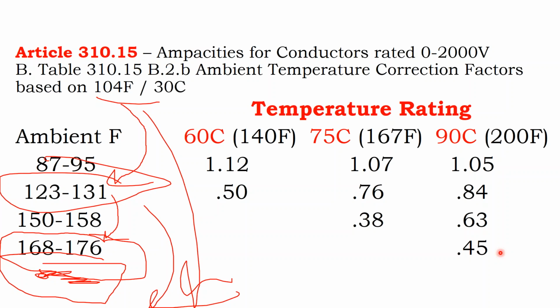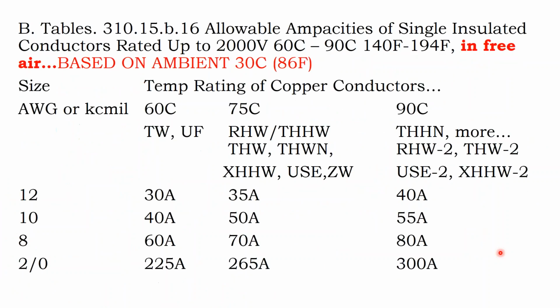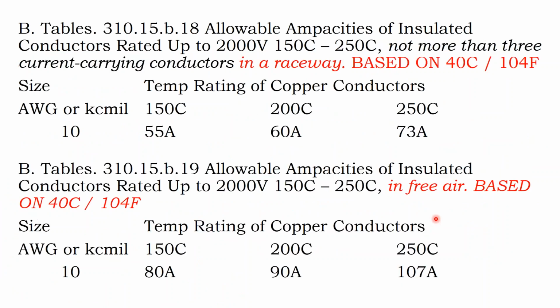And then you go from a non-continuous load to also that the STC rating is messed up. So on DC, you have an additional 25%. That gets it down to 8 amps. And so all of a sudden, we have this big, thick number 10 cable with a robust jacket that, if it were inside the house, could handle all the way up to 73 amps in a raceway. But then you put it on the rooftop with a whole bunch of other conductors in a DC application, and up on the roof, it can only hold 8 amps.